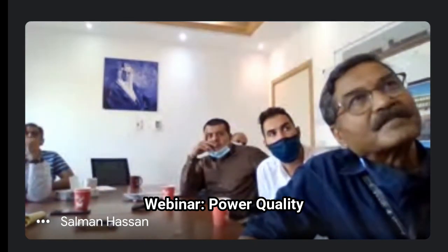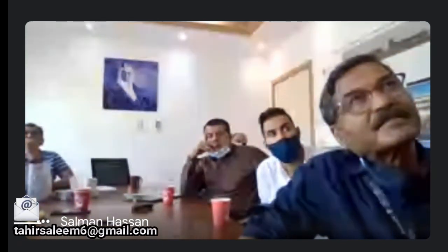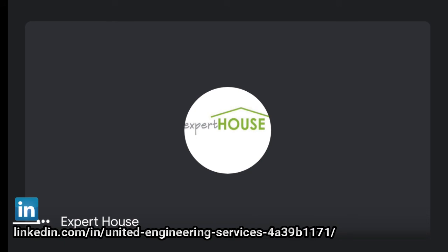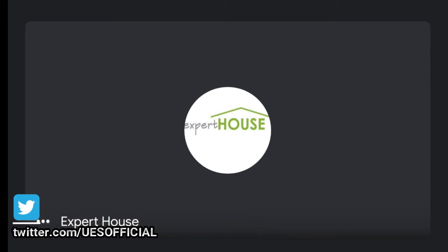Even the management, what happens in Pakistan? The management says, please put this VFD in operation, take the normal supply and put it in operation, and don't consider it a non-linear load. But the design parameters should be according to the requirements of the non-linear load. That is what we maintenance people are not doing. I have worked a lot in the maintenance field, but at that time we didn't know what was there.